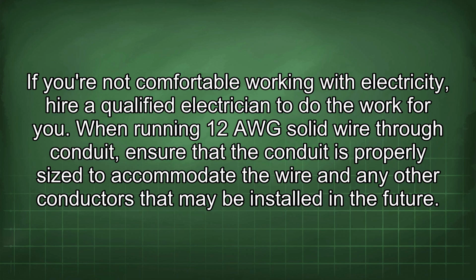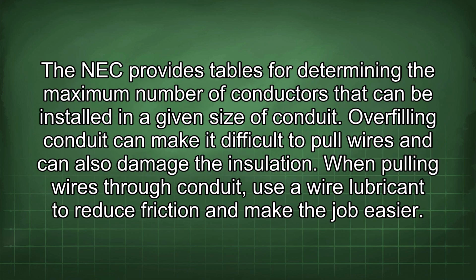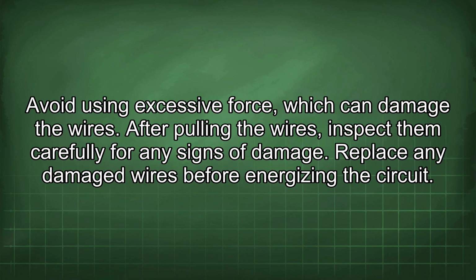When running 12 AWG solid wire through a conduit, ensure that the conduit is properly sized to accommodate the wire and any other conductors that may be installed in the future. The NEC provides tables for determining the maximum number of conductors that can be installed in a given size of conduit. Overfilling conduit can make it difficult to pull wires and can also damage the insulation. When pulling wires through conduit, use a wire lubricant to reduce friction and make the job easier. Avoid using excessive force, which can damage the wires. After pulling the wires, inspect them carefully for any signs of damage.